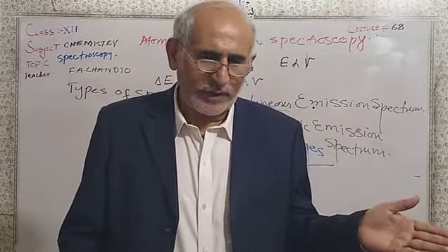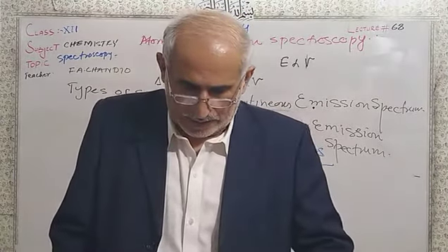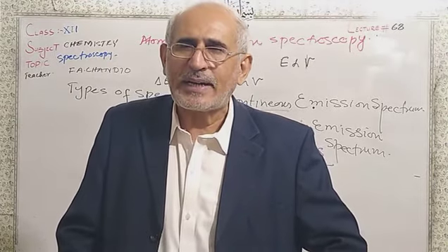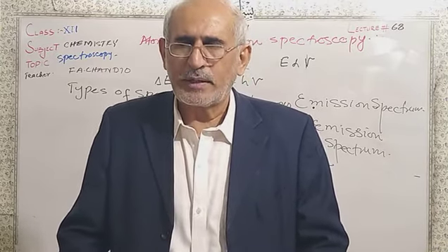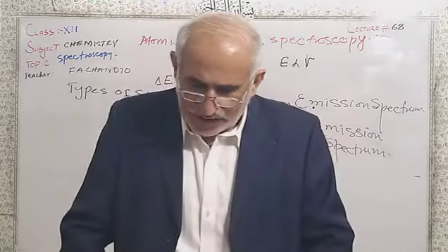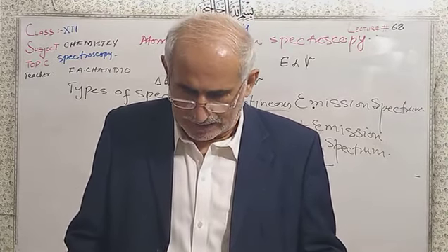So students, there are advantages, but there must be also disadvantages. Disadvantages. The equipment is costly and wide experience is required for successful handling and interpretation of spectra. It means that the chemist, the worker, the engineer who works with this instrument must be a most experienced person, and also it is costly. Recording is done on the photographic plate, which takes some time to develop, print and interpret the results. Radiation intensity is not always reproducible. Relative error exceeds 1 to 2%. The accuracy and precision are not high. So these are the disadvantages in the emission spectroscopy.